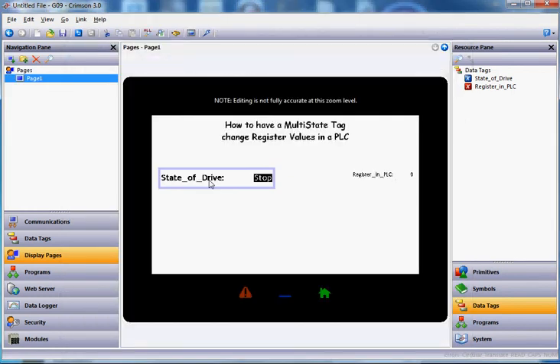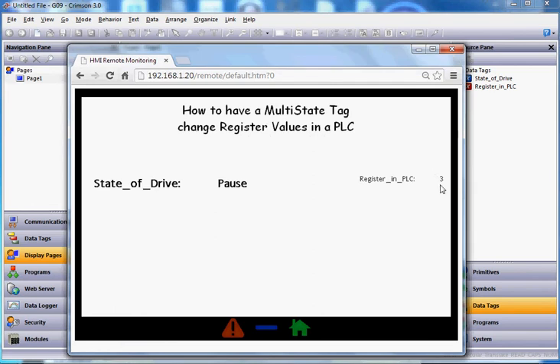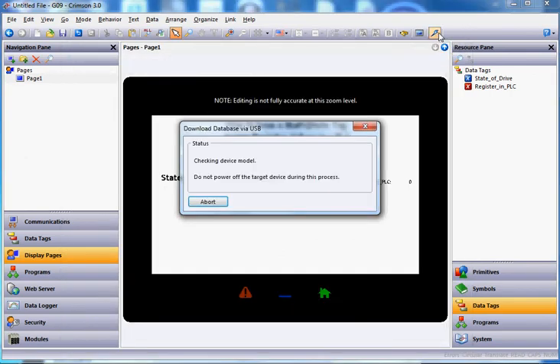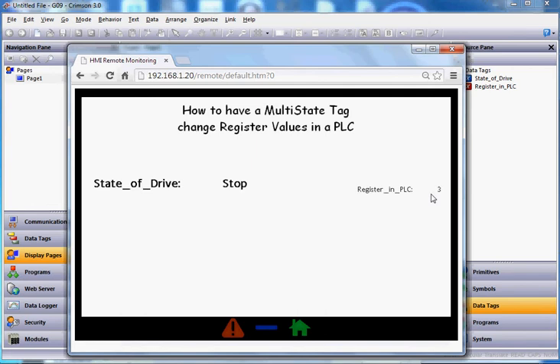I'm going to go back to the program and make a slight change just to trigger a re-download. Before I do, I want to note I'm currently in pause mode — the PLC is at number three. If I download back to the HMI and go back to the web view, notice the register in the PLC is still three because that's where I left it. But a power cycle of the HMI would cause it to come up in a default state. So we really should have a function that loads the current mode on startup — we need something that loads in startup settings.